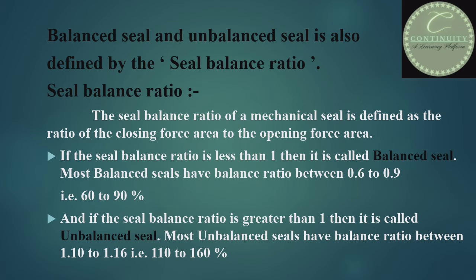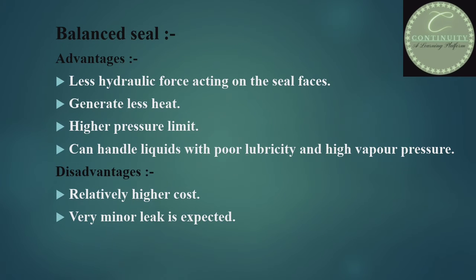Now I will tell you about the advantages and disadvantages of the balanced seal. Its advantages are: less hydraulic force acts on the seal faces because closing force is less than opening force, and due to this it also generates less heat. It can be used for high pressure applications. It can handle liquids with poor lubricity and high vapour pressure. Disadvantages of balanced seal: relatively higher cost, and very minor leak is expected.